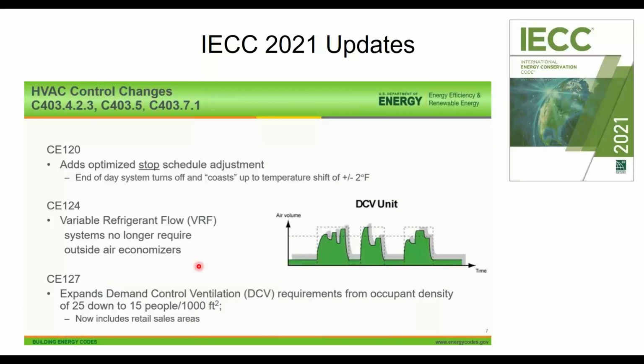Or B, what you have to do is do the energy modeling code compliance path, where you basically model the building as if you built it to code. Then you model it again using your system, in this case VRF, and as long as you exceed it by a certain percentage, 15%, it's considered code compliant. That will no longer have to happen, and VRF will just automatically get an exception for not needing an air-based economizer. Demand control ventilation we've had for a long time in the code as well.